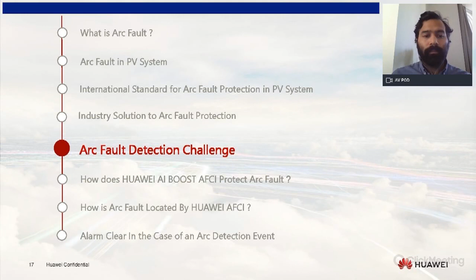But even when you have built-in arc fault circuit interruption in your inverter, there are some challenges. The first one is that the arcing could be read as a high frequency signal between 10 kilohertz and 100 kilohertz, and the AC component of this signal could be analyzed. As you can see here in the picture on the right, we are reading the signal of a no arc situation and an arc situation. We focus on identifying this noise in order to differentiate the two scenarios, and there is a clear difference in the noise and the frequency spectrum. Once we analyze this, we are able to identify there is an actual arc fault.